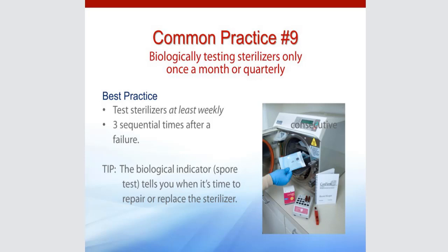If your sterilizer has gone out for maintenance or repair, and when it's brought back, you need to run a BI. If you rearrange your reprocessing center so that you have that one-directional workflow, and you move the sterilizer from one part of the counter to the other part of the counter, you physically picked up the sterilizer or scooted it, you need to run a BI. The other thing that we see that sometimes is common practice is after an office has had a consecutive failure, a BI. So they sent a test in from October the 1st, and they found out that that test failed. So then they did their immediate retest, and that second test failed. If that happens, you are required to do 3 sequential BI tests.